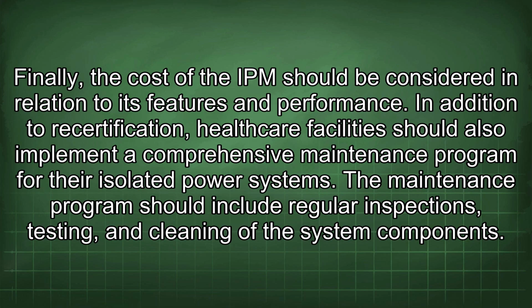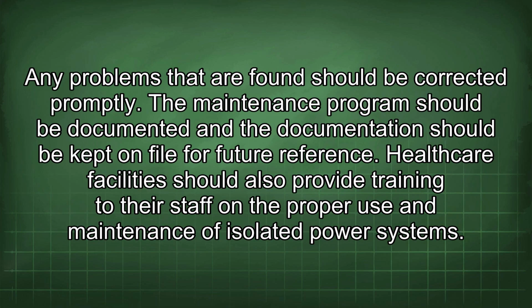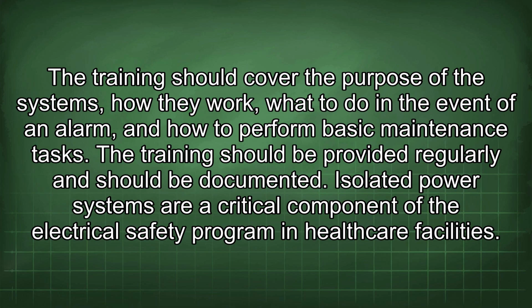In addition to recertification, healthcare facilities should also implement a comprehensive maintenance program for their isolated power systems. The maintenance program should include regular inspections, testing, and cleaning of the system components. Any problems that are found should be corrected promptly. The maintenance program should be documented and the documentation should be kept on file for future reference. Healthcare facilities should also provide training to their staff on the proper use and maintenance of isolated power systems. The training should cover the purpose of the systems, how they work, what to do in the event of an alarm, and how to perform basic maintenance tasks. The training should be provided regularly and should be documented.